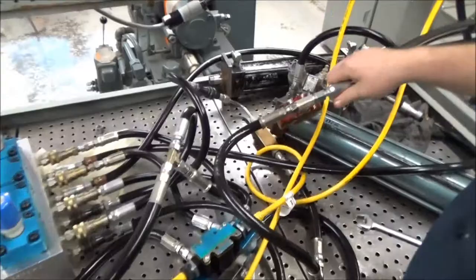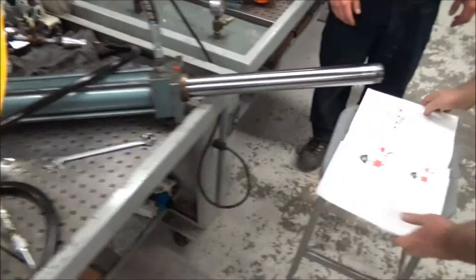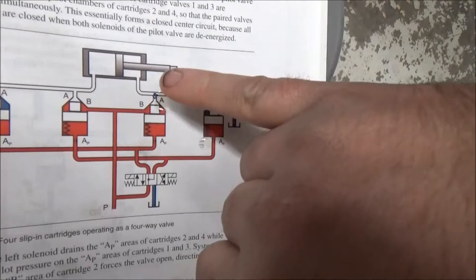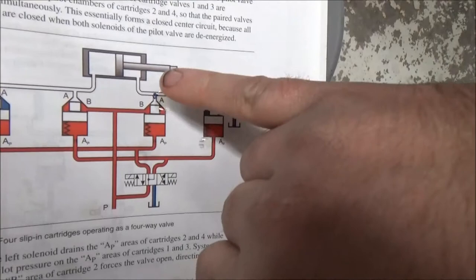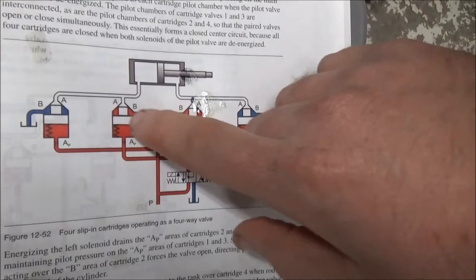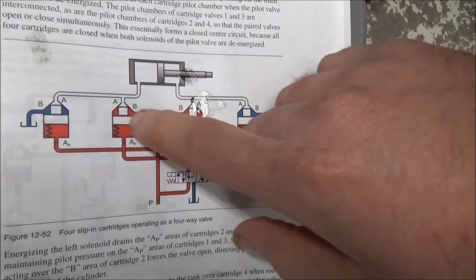We have to add this check valve right here, which is right here on our diagram, because the pressure intensification from the rod is 2 to 1 ratio, so 200 psi here, 400 psi here, and it was actually enough to push open the cartridge valve, and it would regenerate fluid through here and actually speed up the cylinder.